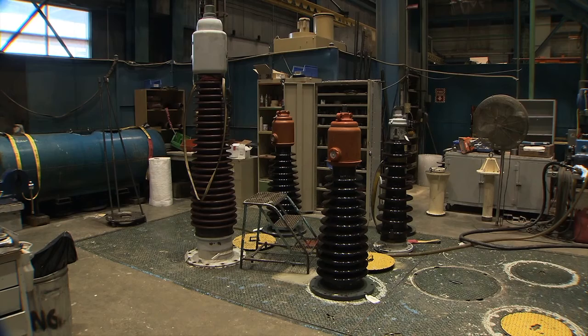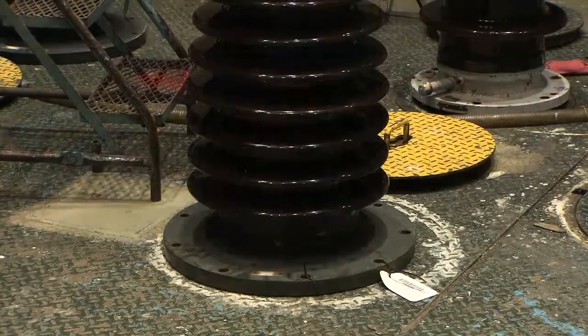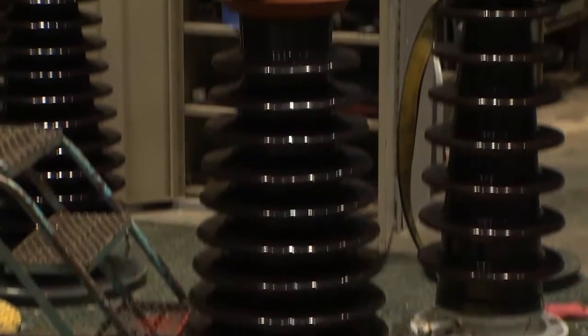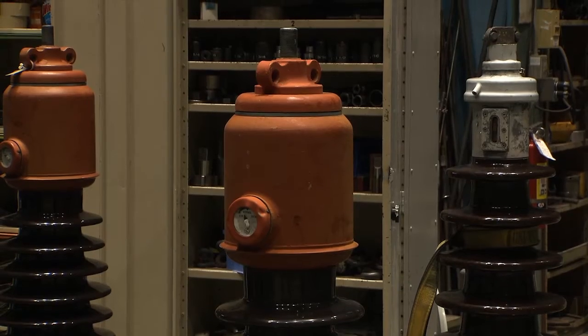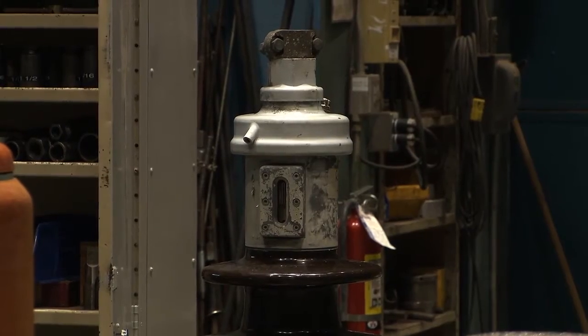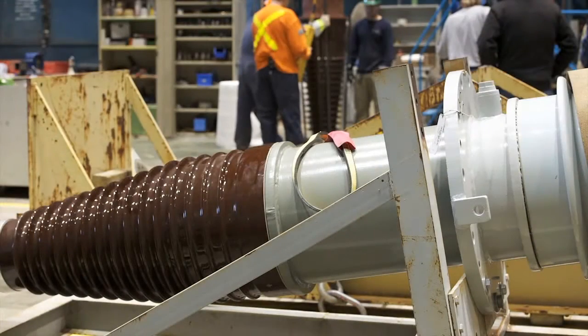Although the bushing that's presented in this module is a capacitance-graded bushing rated for 500 kilovolts and 1800 amps, there are many other types of bushings that will need to be refurbished in the bushing shop. During their very early years, bushings were in effect nothing more than a hollow porcelain shell filled with transformer oil and through which a conductor passed. Alternatively, they consisted of solid resins surrounding the conductor. Such simple bulk and solid type bushing designs are in fact still widespread today at the medium voltages and in some cases even up to 110 kilovolts.